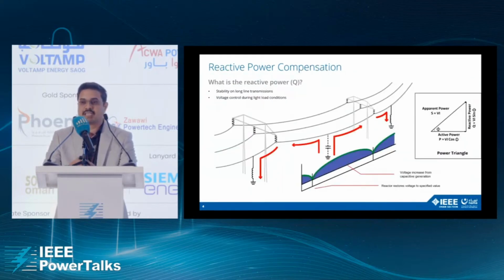So here, what is reactive power and why is the compensation of reactive power required? On the right-hand side, you can see we have this power triangle, where the apparent power is the total power supplied to the system. Active power is the power which does the actual work in the system. And then we have the reactive power. Reactive power does not do the actual work, but it is very important to create magnetic fields, to maintain grid stability, and to maintain voltage across the grid.